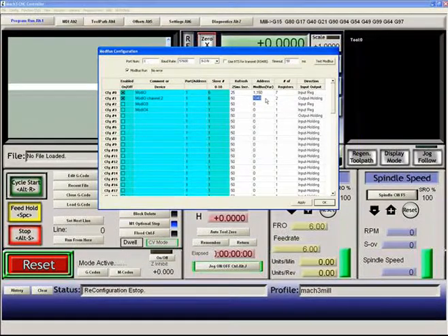My Mod I/O is currently running at the moment and is every 25 milliseconds transferring in the first 7 registers of the Mod I/O, and every 50 milliseconds it is sending 2 registers out to the Mod I/O. And these are going into configuration 0 and 1. Configuration 0 is receiving data. Configuration 1 right now is set up to send data. As I said, you can set up to 63 of these configurations, and thus you can send whatever memory words you want at whatever timing intervals you want back and forth from any PLC.